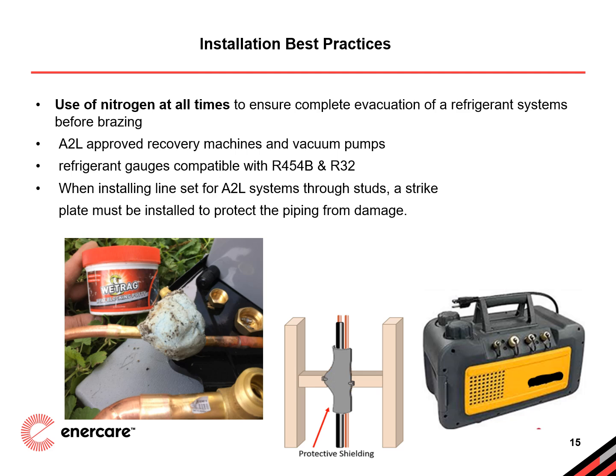Only use A2L approved manifold gauges, recovery machines, and vacuum pumps to guarantee compatibility and safety when working with these refrigerants. Review and validate with the manufacturer's literature or vendor that the tools and equipment being used are A2L approved. Additionally, install striker plates where line sets run through stud bays to prevent accidental punctures during or after installation. These plates provide a layer of protection and align with our goal of treating every home as our own by maintaining a safe, durable system design. Maintaining these practices raises the bar for quality and long-term system performance, and what sets us apart from every other contractor in the field.